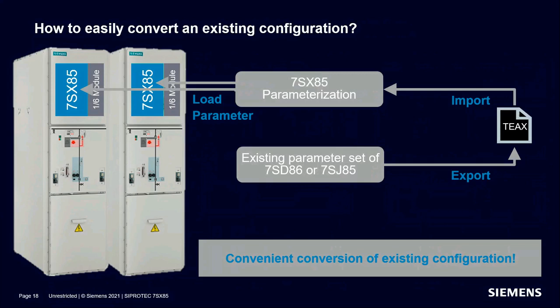So finally, what benefits do we see the new 7SX85 can offer for you? First, a consequential use of the 7SX85 reduces dramatically the number of device variants. This facilitates the daily work in many situations, having to deal only with one device type. Then, having installed only one device type obviously reduces the number of spare parts to a minimum. Before, we showed you that you can save a lot of engineering work by configuring a common part for all different typical applications only once, and then reuse this configuration as a basis for all feeder typicals.